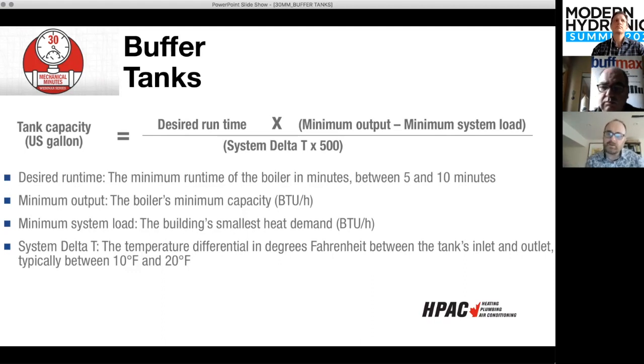We're saying, okay, what's our minimum runtime and what's our minimum firing rate? And we can go through the math. I can do a quick example if you like. I've just got one here on my phone I can pull up. For example, say we've got an 87,000 BTU output boiler, and the minimum firing rate is 20,000. We've got a 5-to-1 turn down ratio in this case. For a minimum runtime of 5 minutes, I want to go at least 10, so we're going to double this. The smallest zone is 2,000 BTUs.